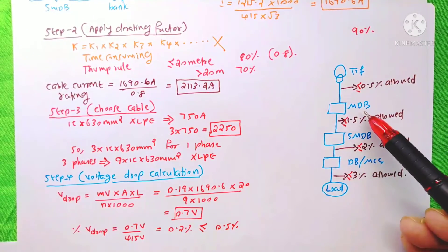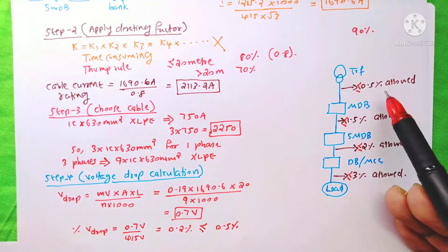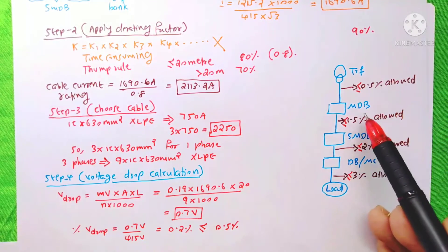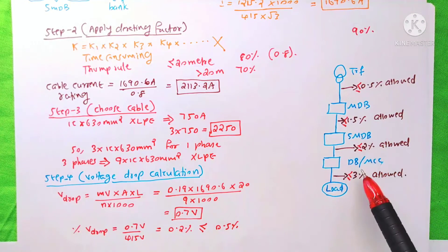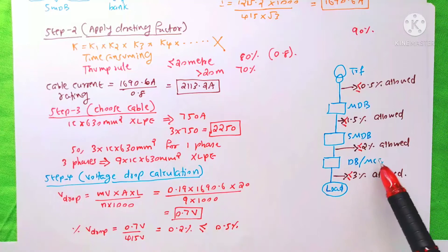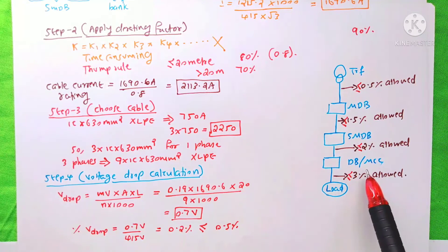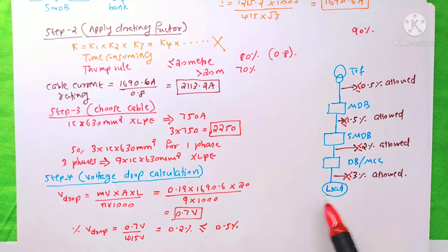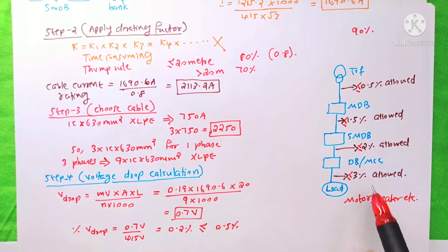Between transformer and MDB, the maximum allowable voltage drop is 0.5%. Our 0.2% is less than 0.5%, so the cable passes the voltage drop check. Between MDB and SMDB, 1.5% is allowed; between SMDB and DB or MCC, 2% is allowed; and between DB/MCC and the final load (motor, heater, etc.), 3% is allowed.